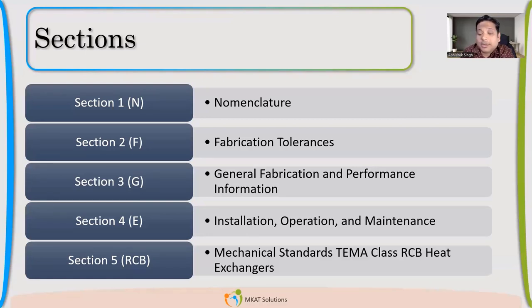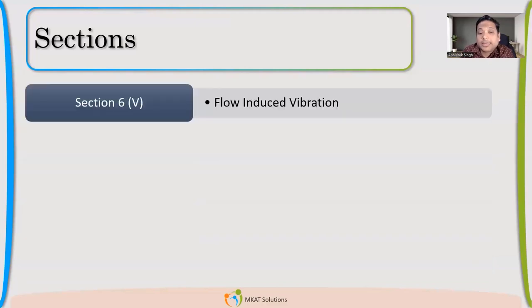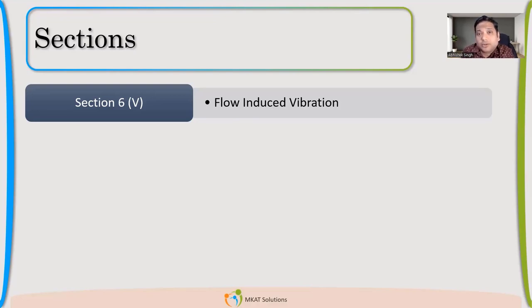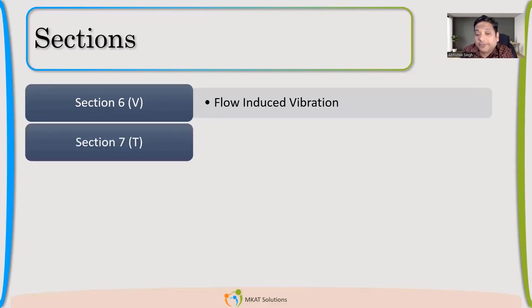Section five is very, very important — all your design-related requirements are mainly found here: shell thickness, minimum shell thickness requirement, tube thickness, baffle thickness, tie rod numbers, and lots of other things. Section six is also very important — it's related to flow-induced vibration. It talks about tube vibration and baffle damage due to vibration. There are four methods used to determine this vibration, including the effect of vortex shedding — everything is given in this section.